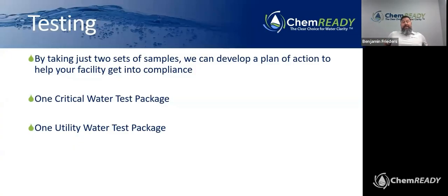Look, by just taking 2 sets of samples, 1 critical water test package and 1 utility water test package, we can develop a plan of action to help your facility get into compliance, right? Not only get into compliance, but develop a plan to talk to the people in charge of your budget and figure out a reasonable plan that the Joint Commission or Medicare, Medicaid will accept when they come to audit your facility.